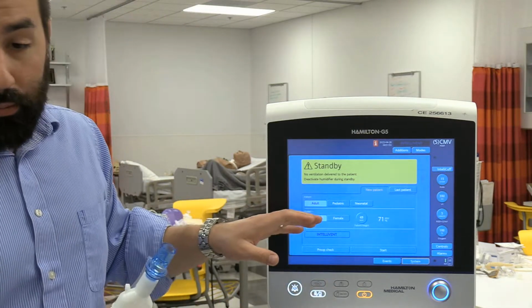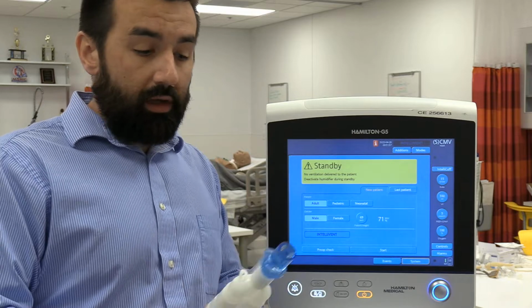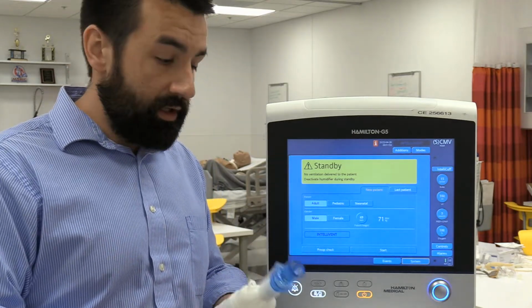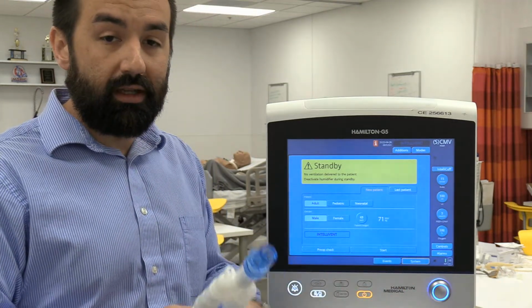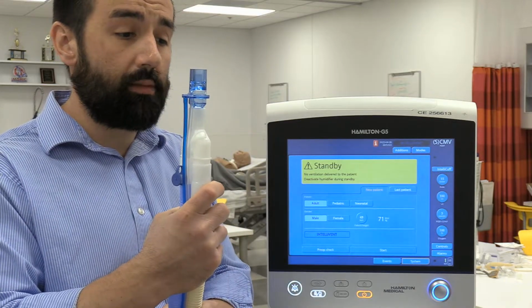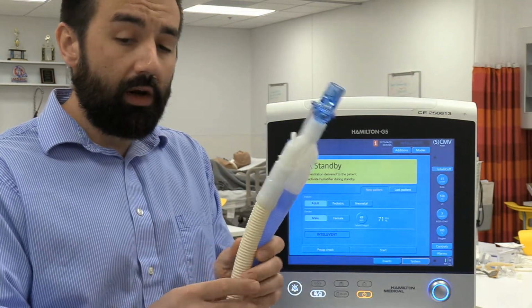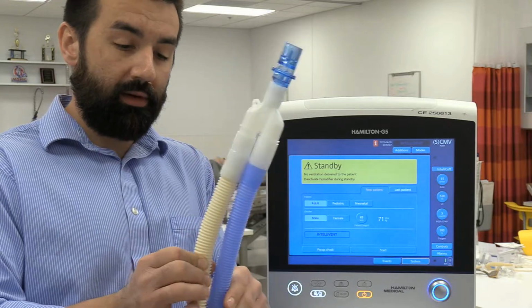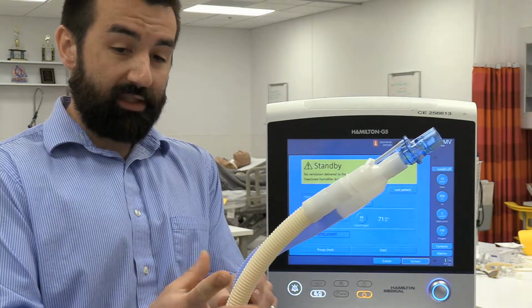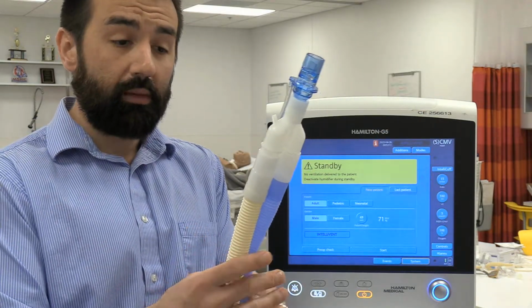I'm going to show you how to do a pre-use check here. What a pre-use check does is make sure the ventilator is functional, make sure you don't have any massive leaks in the system, and make sure everything's calibrated and ready to go for a patient. It also does something important that we take for granted on modern vents, and that is compensating for what we know as tubing compliance or circuit compliance.